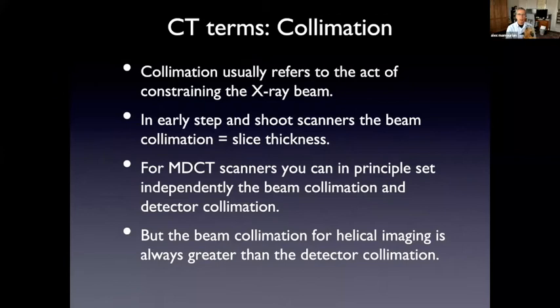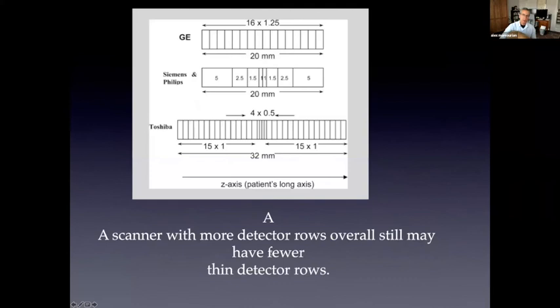Another term that will come up is collimation. This refers to the constraint of the x-ray beam. So there's x-ray beam collimation. In the early scanners, the beam collimation was the same as the slice thickness. It's different for multi-detector scanners because even though in theory you can set the beam collimation differently than the detector collimation, the beam collimation has to always be greater than the detector collimation. So usually the beam collimation is always slightly wider than the detector rows.